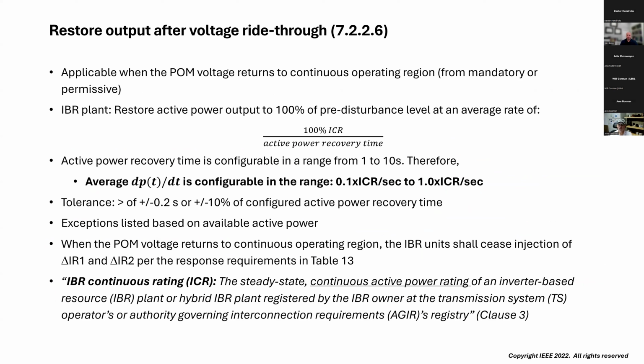So now we know what type of current we need to inject, how much, and what the time domain response needs to look like. Once the disturbance is removed from the system, so the POC voltage goes back to the continuous operating region, the IBR plant needs the capability to restore active power at an average rate. If you work through all the math here, what it really winds up being is that this average rate of active power recovery is going to be configurable in this range from 0.1 per unit per second to 1 per unit per second.